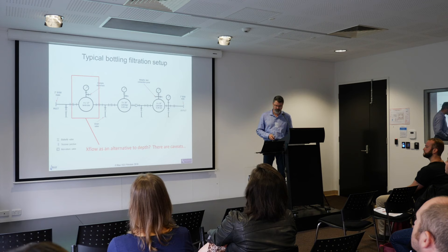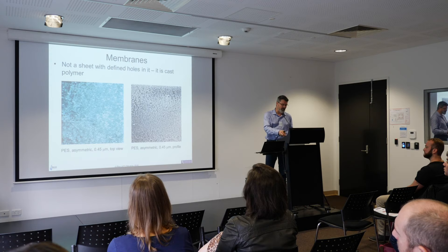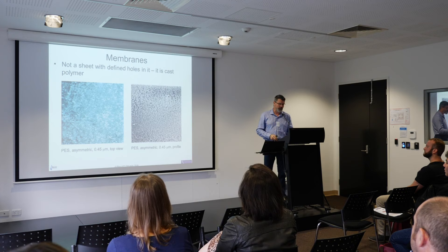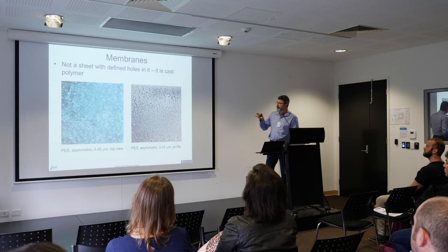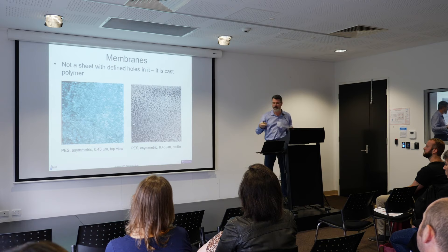For those who haven't seen this before: a lot of people think of a membrane as something like a sheet of paper with 0.45 micron holes punched in it. It's not like that — it's much more like a sponge or a piece of bread. If you look at a membrane sheet from on top you'd see something like the left-hand image, and from the edge, something like the right. Both are PES — polyether sulfone — which is pretty much the industry standard these days. Ten years ago it used to be nylon, but that's gone the way of the dodo.